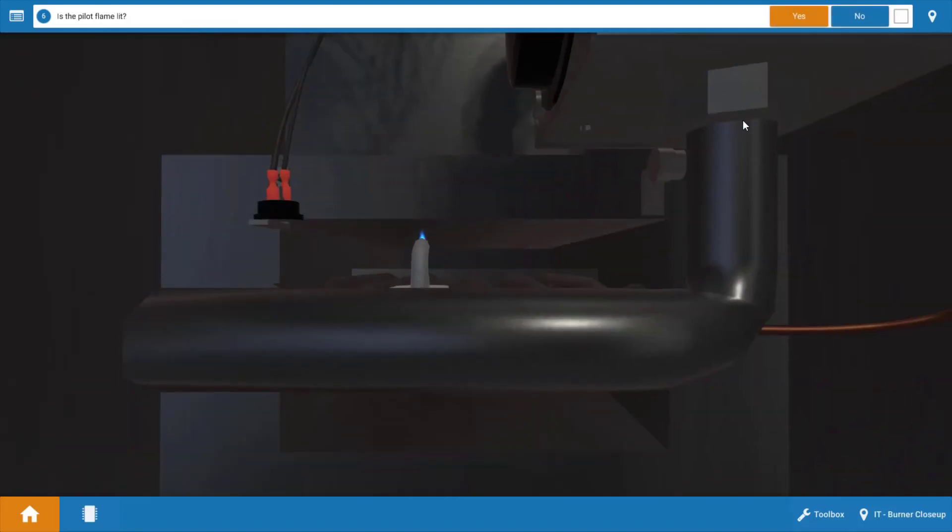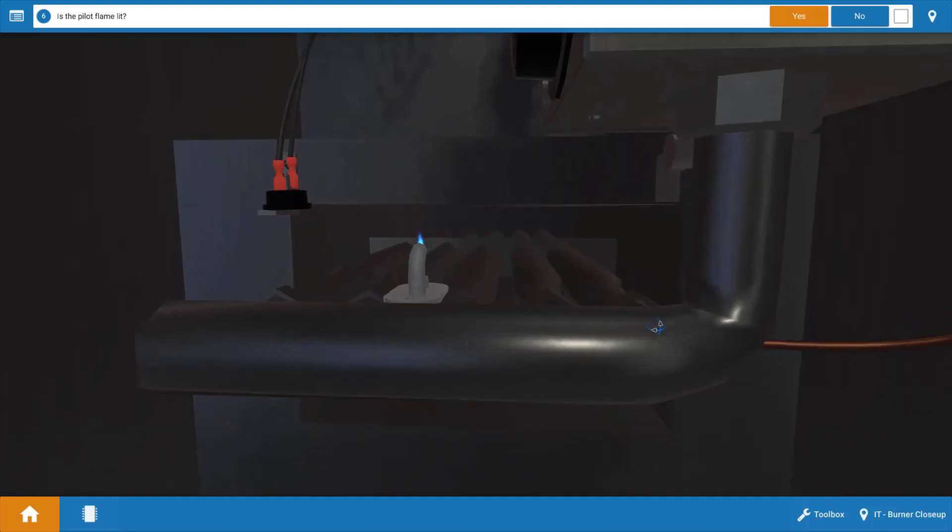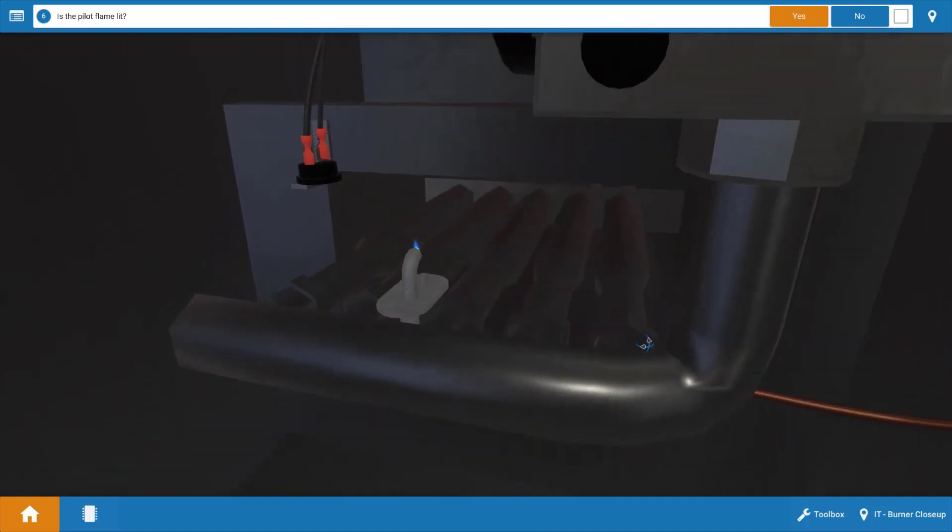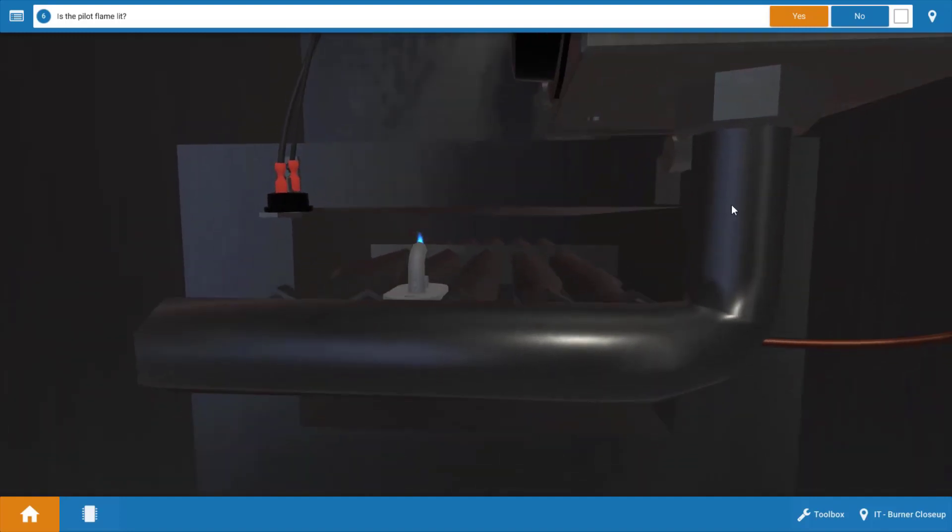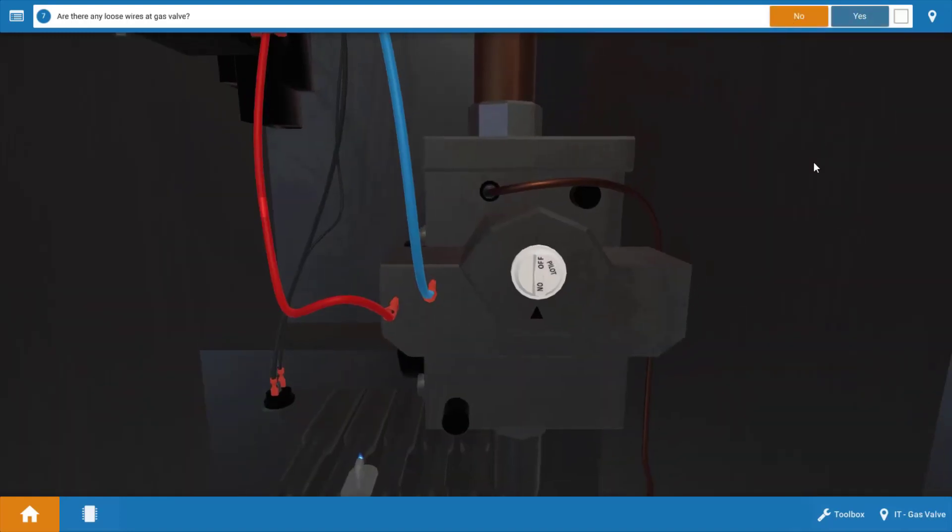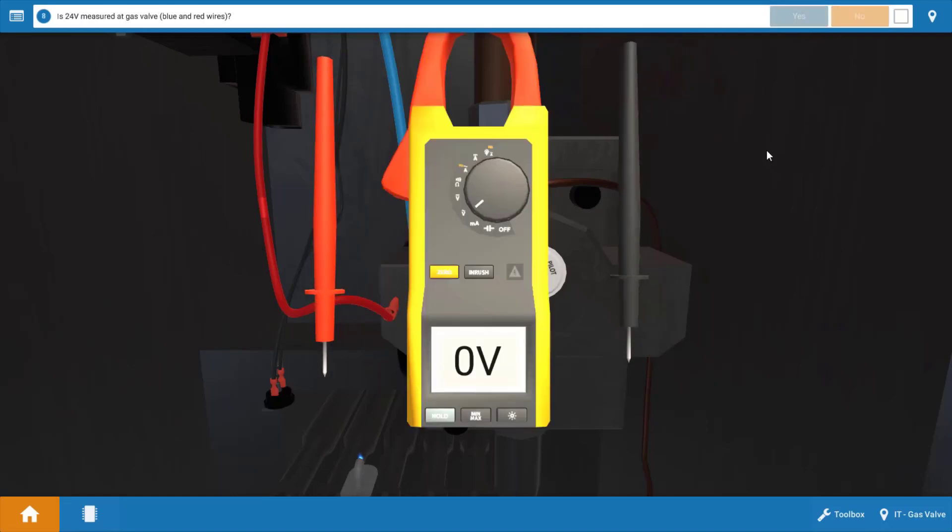Next, we've already verified that the pilot was lit. We'll just take another look just in case you didn't see it the first time. So our pilot's lit. Next, we want to inspect for connections at the gas valve. Now it appears that all the connections at the gas valve are secure, so there's no loose wires.